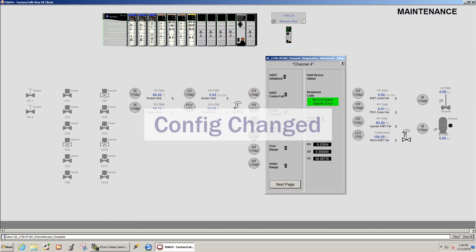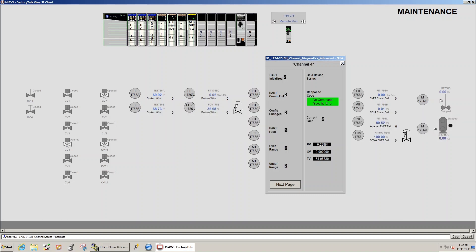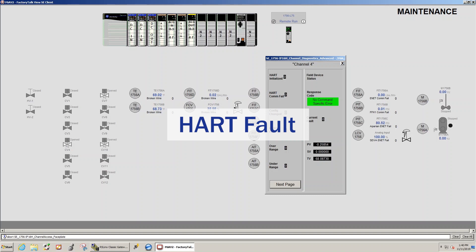Config changed. The field device configuration has changed and the new field device configuration information can be obtained from our module via a get device info SIP message which will clear this bit. HART fault indicates a problem with the HART data from the field device on our channel.